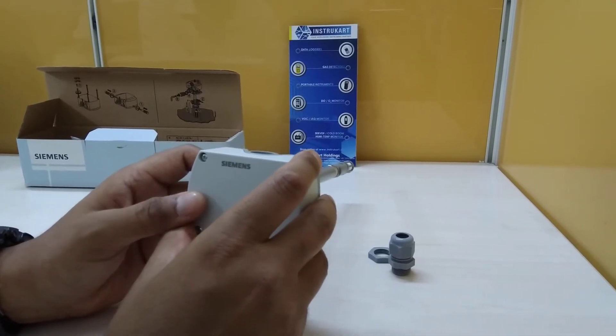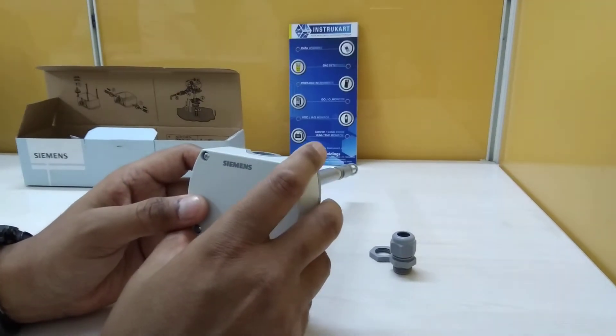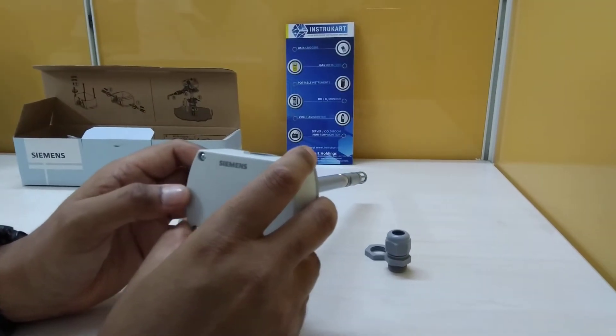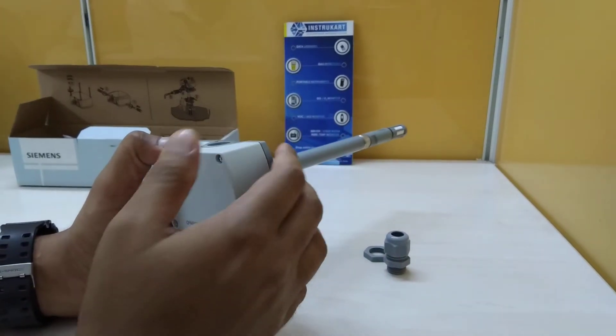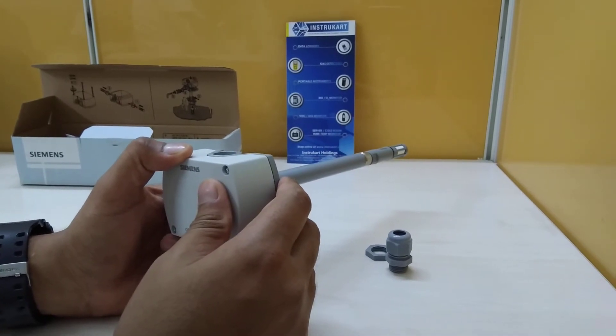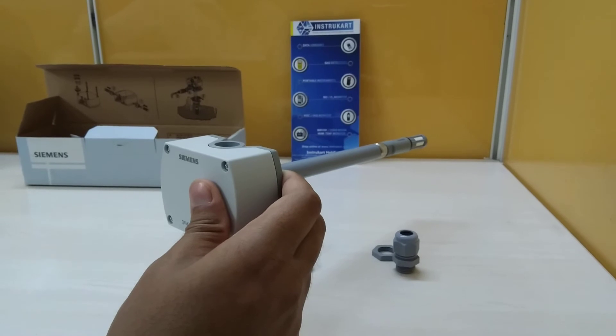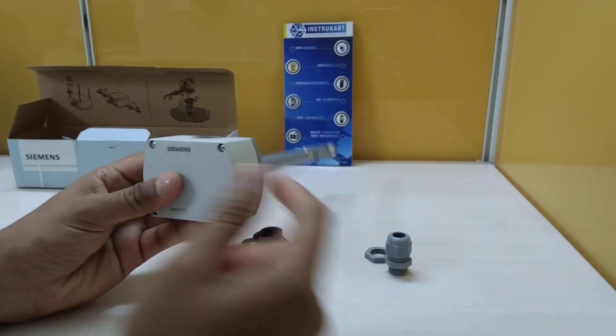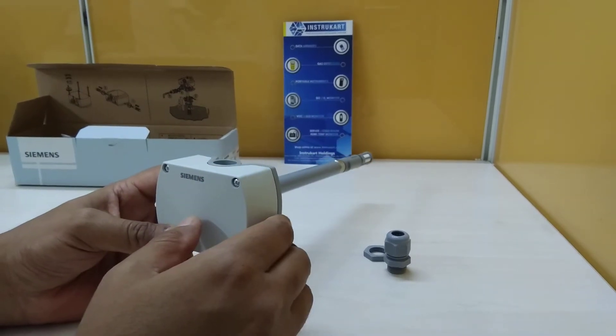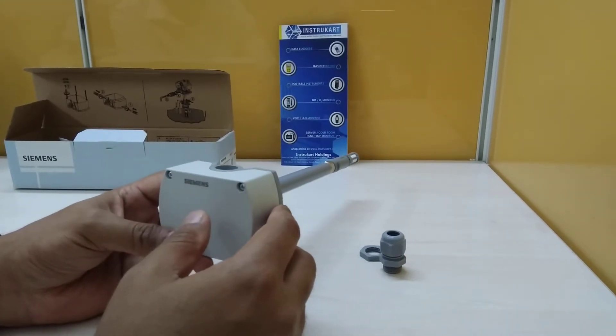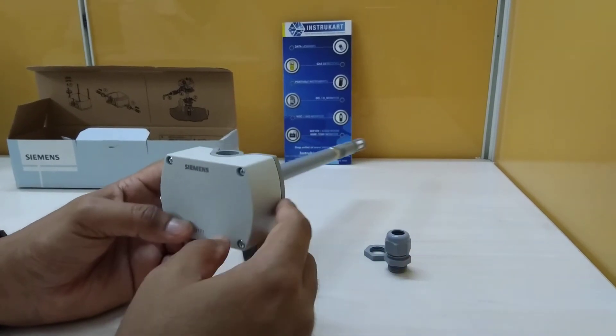And the accuracy for temperature is 0.8 degrees Celsius and RH is plus or minus 2 percent. This has got an immersion length of 90 to 206 mm and this has got a 4 to 20 milliamps output where you can take the data to your building management system through this 4 to 20 milliamps instrument's output.